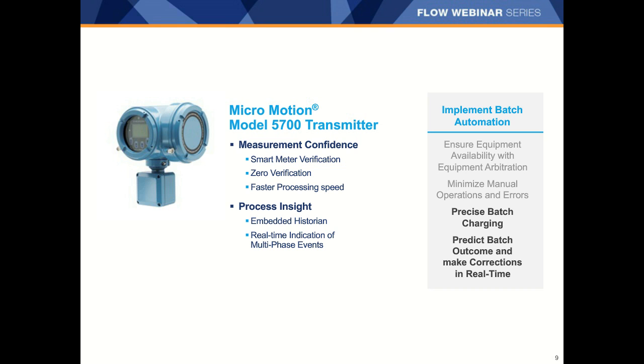And while Micro Motion is the best in entrained gas handling capability on the market, we've also included real-time indications of such multi-phase events. A new software feature, two-phase flow indication, is aimed at bringing more concise information to users about the condition of their fluid. Whether you have a single phase, moderate entrainment that may impact your accuracy, or severe entrainment that will impact both accuracy and repeatability, you can get the notification via display, digital registers, or mapped to an analog output.